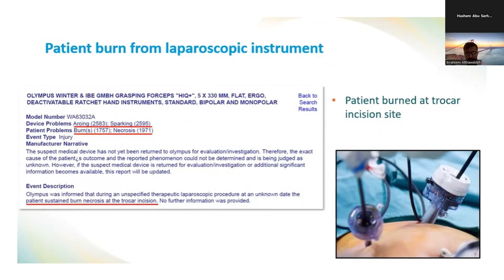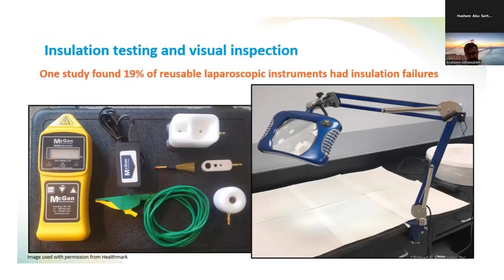Here is another consequence or injury that happened. Patient burned from laparoscopic instrument. And later, after this happened, studies have appeared, and in one study they found 19% of reusable laparoscopic instruments had insulation failures. And here is the insulation testing and visual inspection, tools that needed to be used for every laparoscope after this incident started to happen. As you can see, this example is finished.